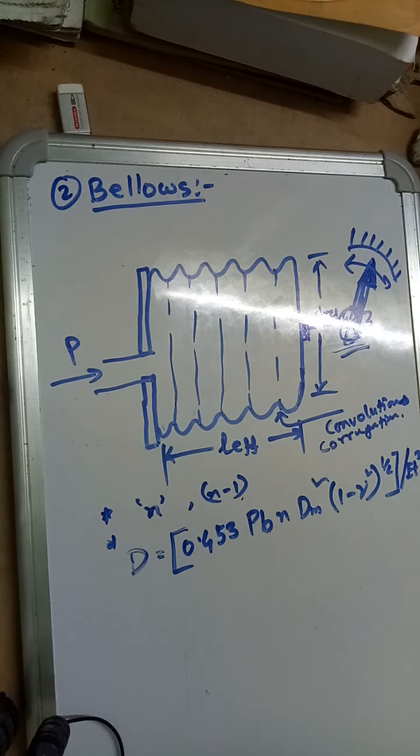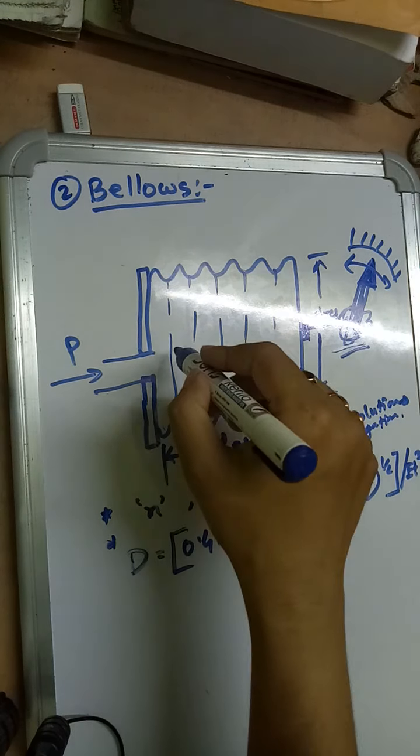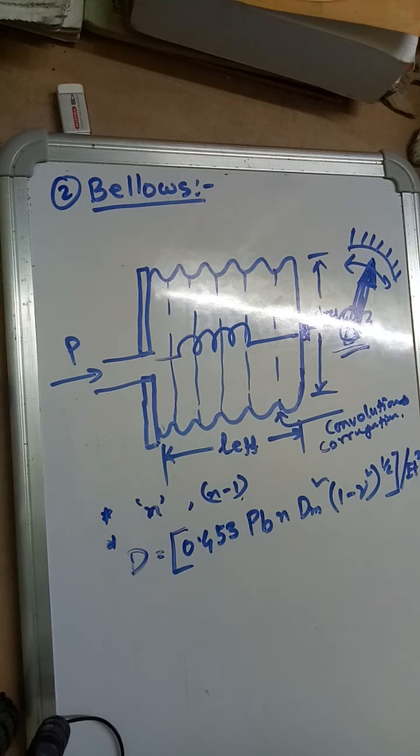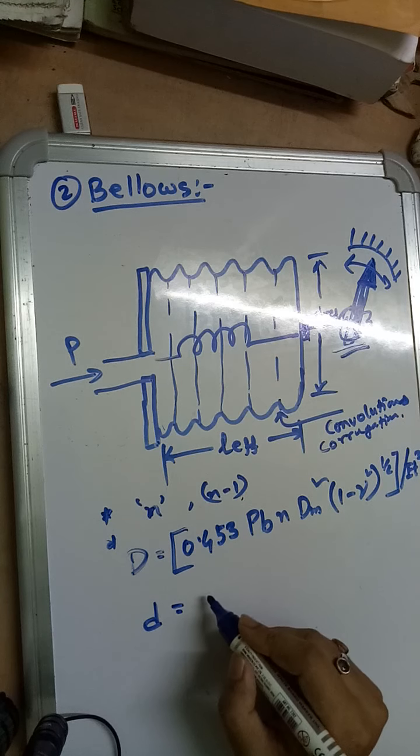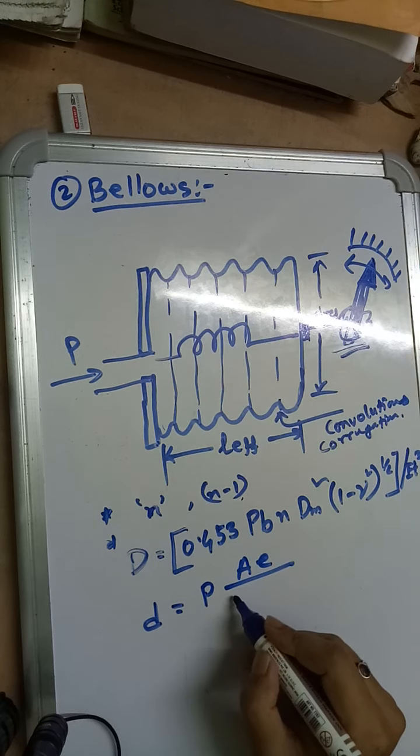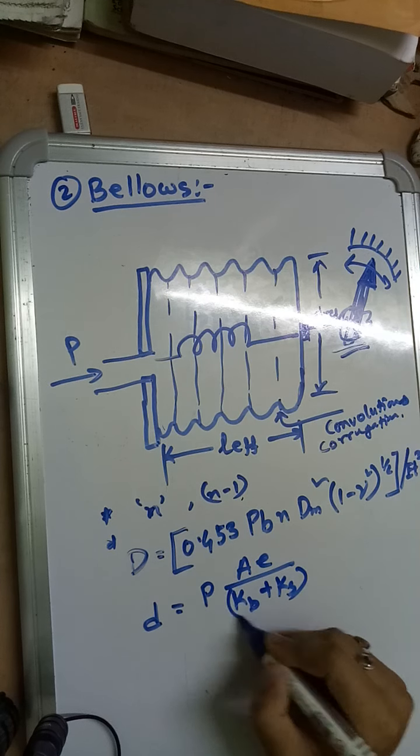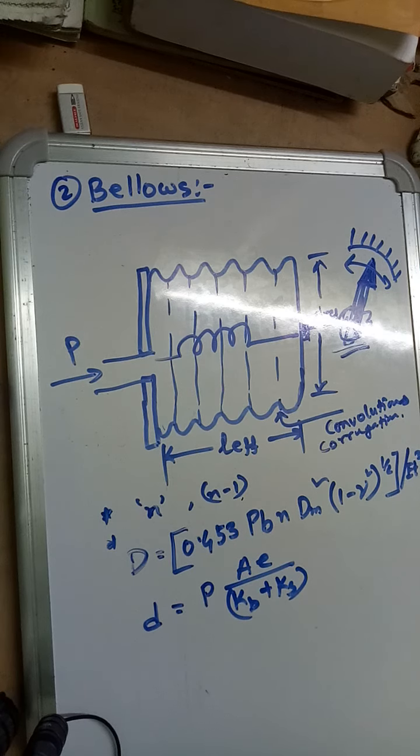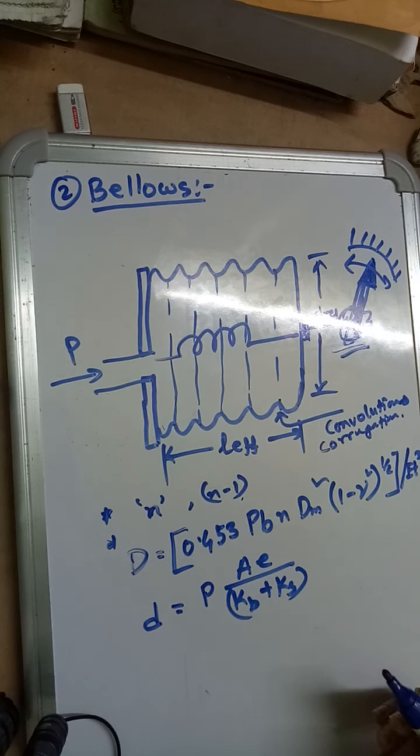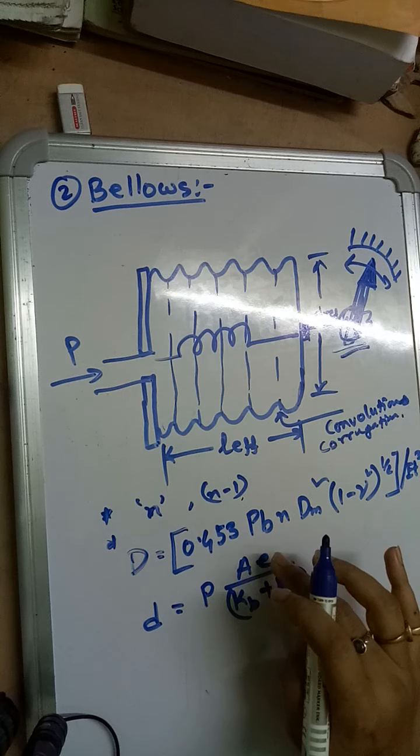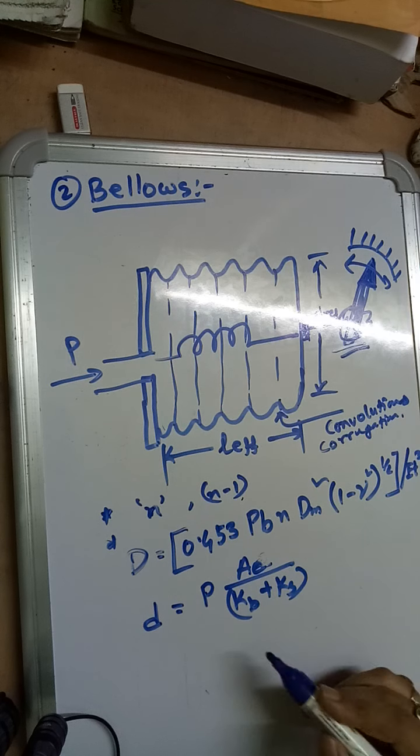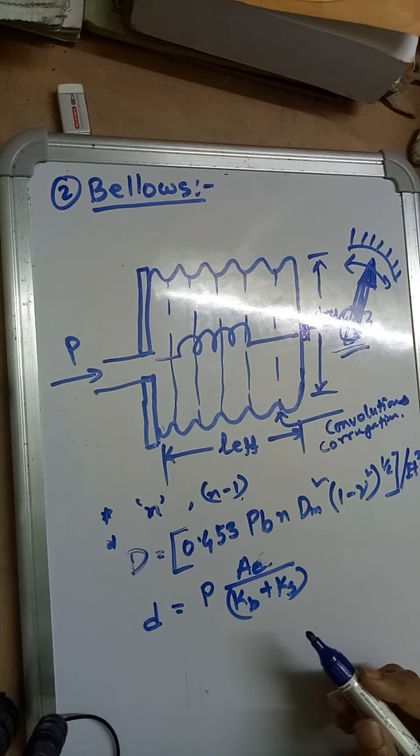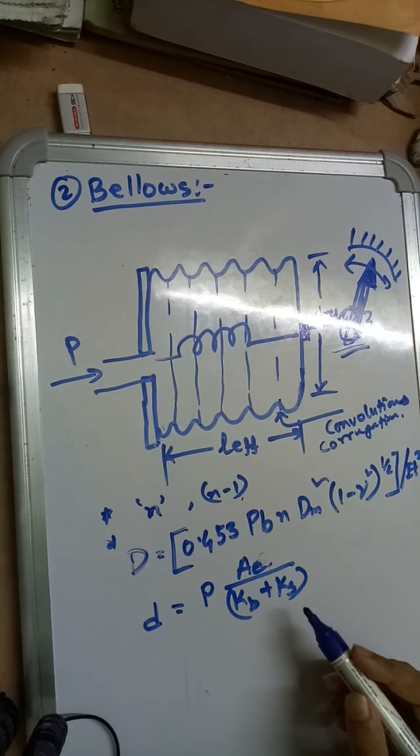This is one empirical formula. There are several empirical formulas. The deflection of bellows when supported or opposed by spring - if the bellows is connected to a spring inside - is given by d = (p × A_e) / (k_b + k_s), where d equals deflection of bellows, p equals applied pressure, A_e is the effective area of bellows, k_b equals force constant or spring rate of bellows, and k_s equals force constant or spring rate of the retaining spring.